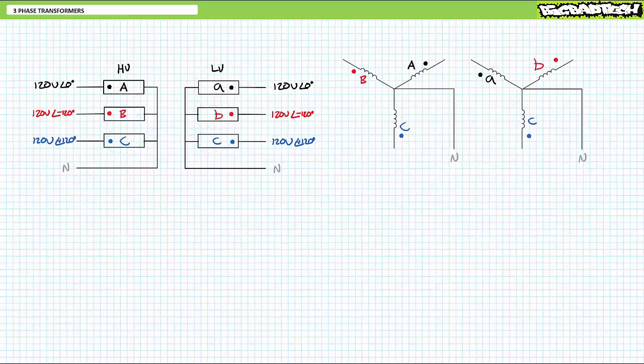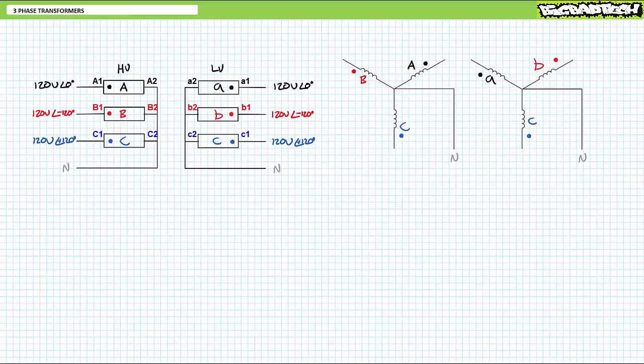Using the simplified connection diagram gets the same point across using far less space and unnecessary complication. You may also see simplified connection diagrams using terminal numbers: A1 and A2 for the ends of primary high-voltage winding A, and a1 and a2 for the ends of secondary low-voltage winding a, with similar terminal numbers for the b and c windings. These numbers can clutter diagrams, so typically just capital and lowercase letters are used, clearly indicating which end of a particular winding has or does not have a phase dot.